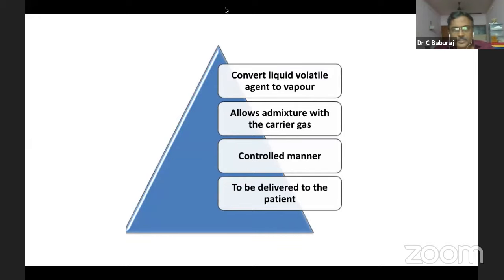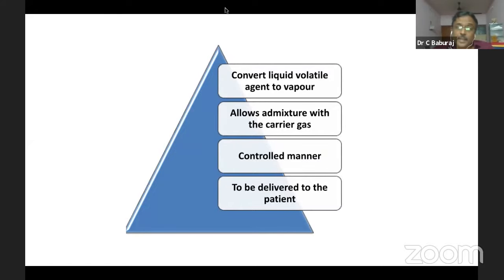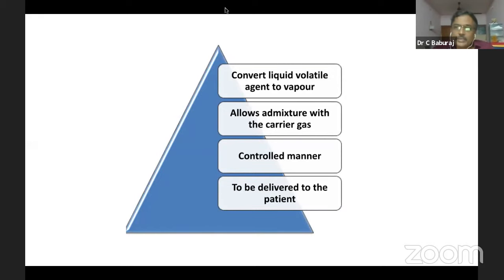There are different stages in the functioning of a vaporizer. First, the liquid volatile anesthetic is converted into vapor. Second, this vapor is mixed with carrier gas — carrier gas can be oxygen, air, or oxygen-nitrous oxide. Third, this is to be delivered to the patient in a controlled manner. That means if you are planning to give one percent halothane, that one percent halothane should be delivered by the vaporizer.